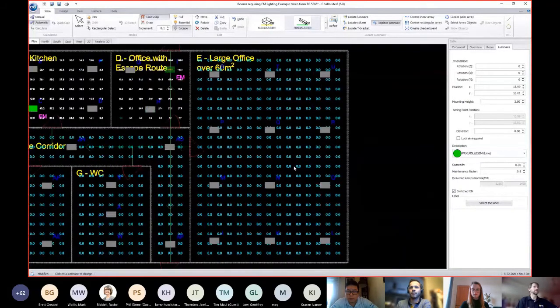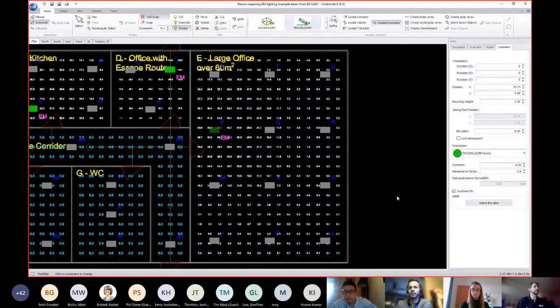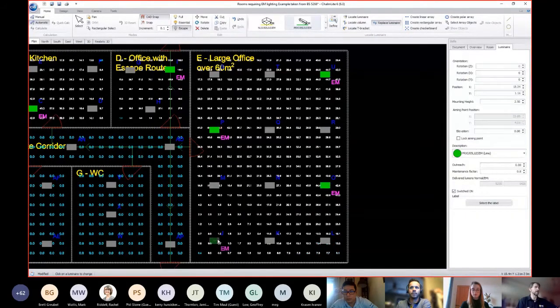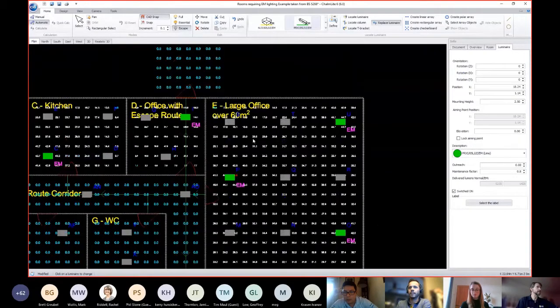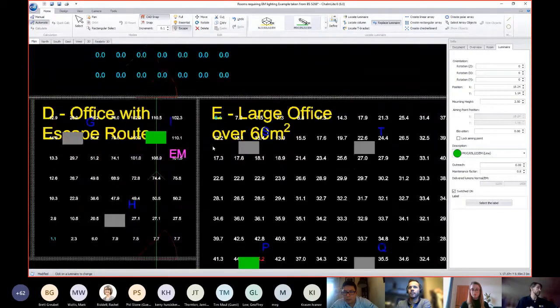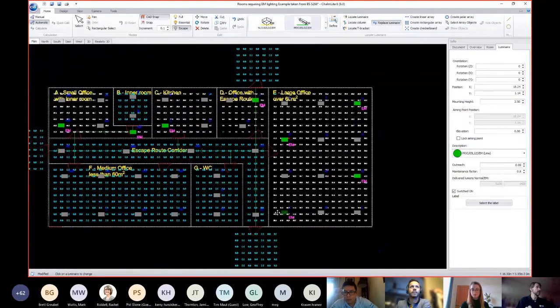Moving on to this big room. This is a big office, over 60 square meters. We're going to have to light this all the way to every corner with a 0.5 lux. So how I would do it is I would light the first one near the escape door, and then make sure that every area is covered by 1 lux minimum. Sorry, half a lux minimum. And our minimum level there, I think, in this little corner, is 6.1. So we're well within the limits.